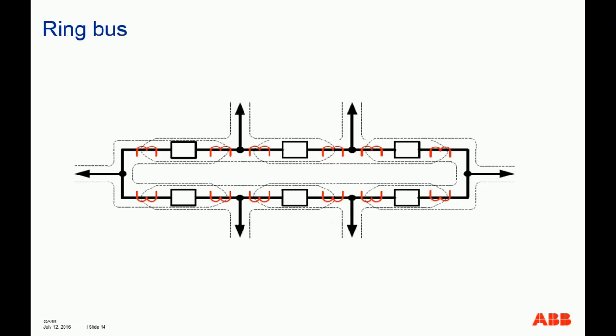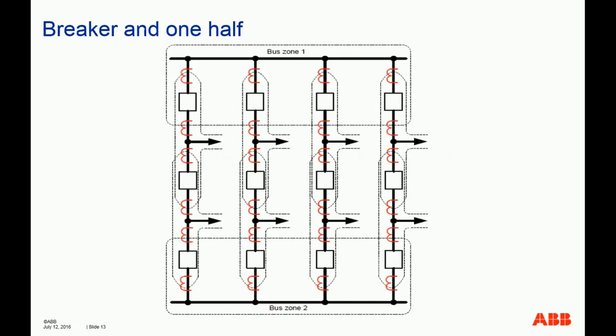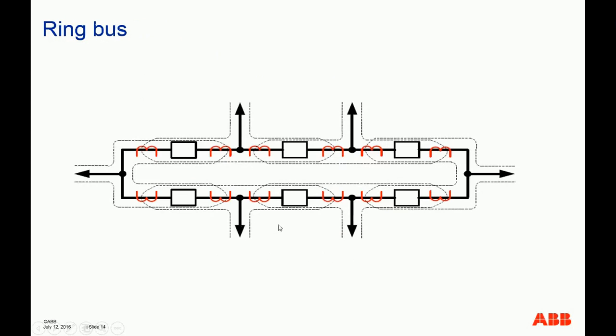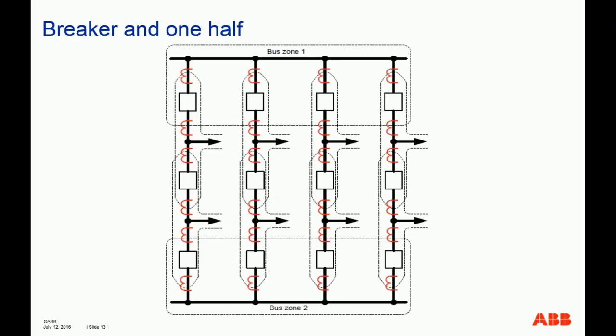Ring bus. This is also quite typical in North America. However, the difference between this and the previous one, sorry, I forgot to mention for the previous one, is that you can see these two dedicated bus bars for the breaker and half scheme. It will require its own dedicated bus protections. However, the bus stubs here can be protected by the equipment protection. If it's a transformer, the transformer protection can take care of and protect these small bus sections.